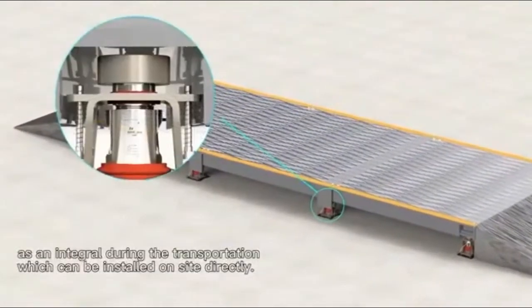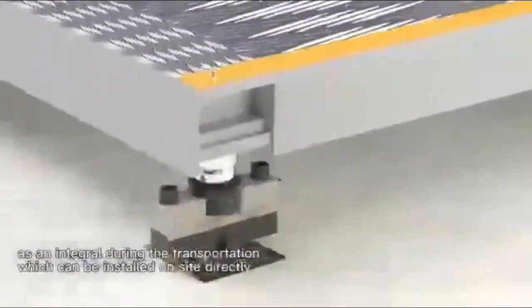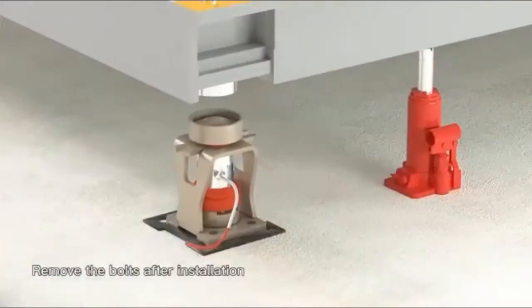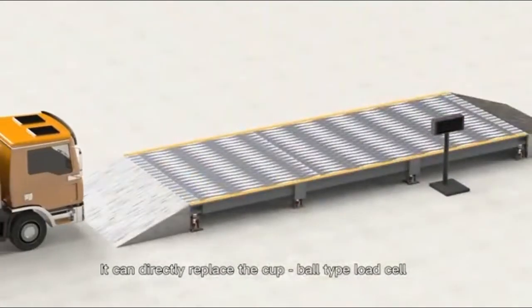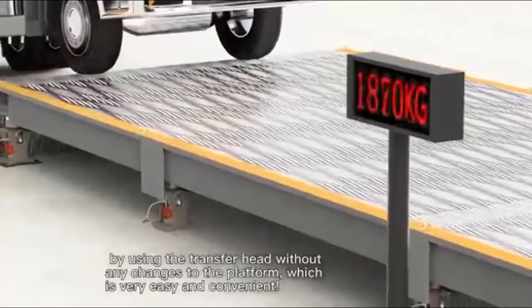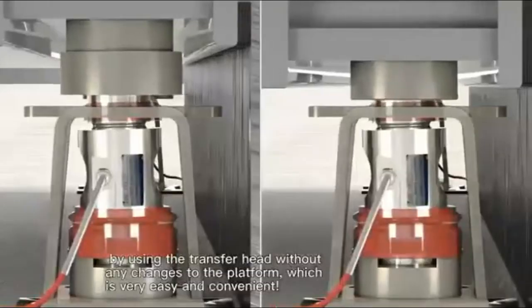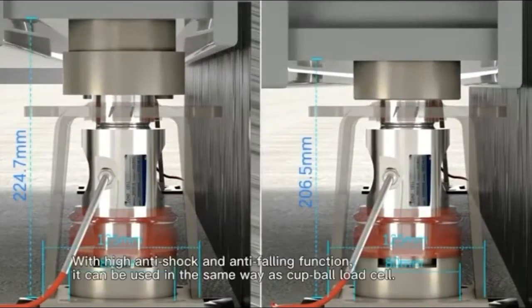It can be installed on-site directly. Remove the bolts after installation. It can directly replace the cup ball load cell by using the transfer head without any changes to the platform, which is very easy and convenient with high anti-shock and anti-falling function.